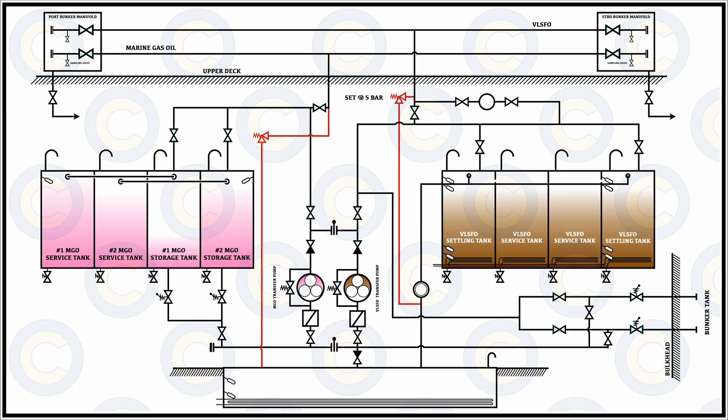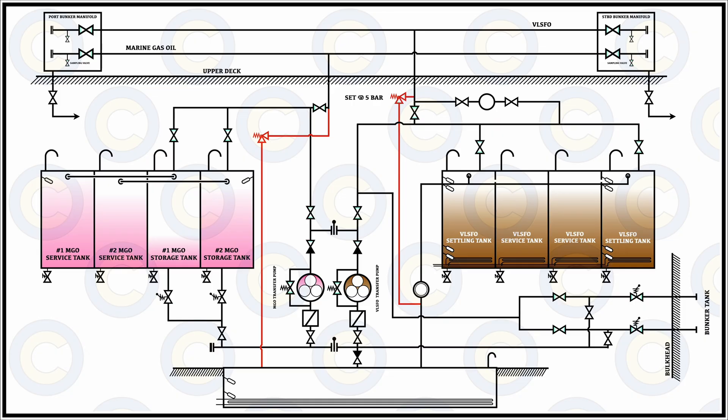It can also be seen that there is a line bifurcating from the main filling line on both MGO and VLSFO side. This line contains a relief valve sort of assembly which is spring loaded and set at a default pressure. Why this is, is because our bunker lines are statically tested at a certain pressure, and to avoid over-pressurization and then later on any spill of oil within the engine room or externally as well through these lines, we have this assembly that would then relieve and take the oil into an overflow tank, may it be on the gas oil side or on the heavy oil or LSFO side, and then make sure that the lines are not over-pressurized and there is no overflow happening.